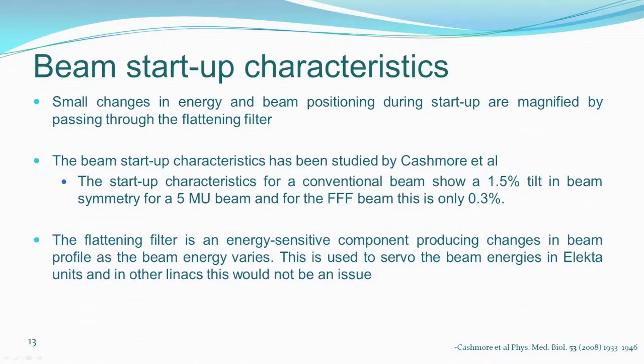And the other important thing is the beam startup characteristics. When we started doing IMRT, when we started delivering small MUs, we were worried about the startup characteristics of the linear accelerator. Small changes in the energy and beam positioning during startup are magnified if you have a flattening filter. So when you don't have a flattening filter, this is not very high. The startup characteristics for a conventional beam show only about 1.5% tilt in the beam symmetry for a 5 MU beam, whereas for a triple F beam, the same thing shows only 0.3%. This is again the study by Cashmore et al., which was published in PMB.